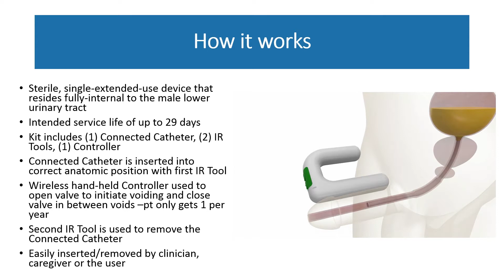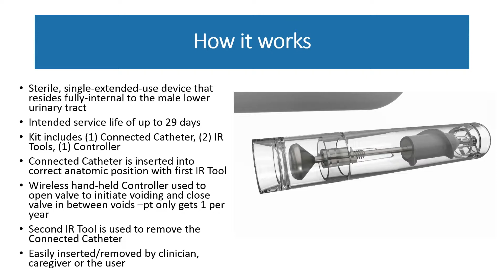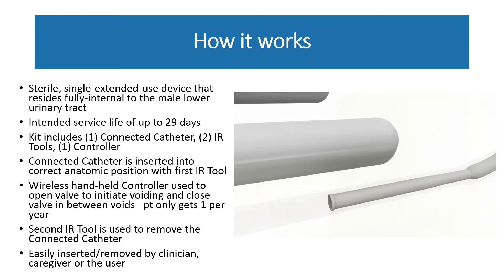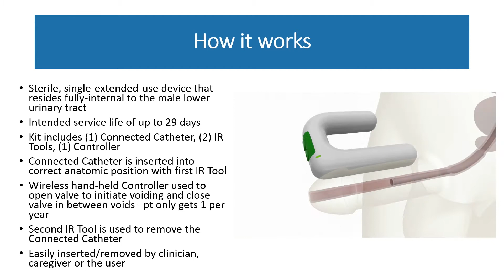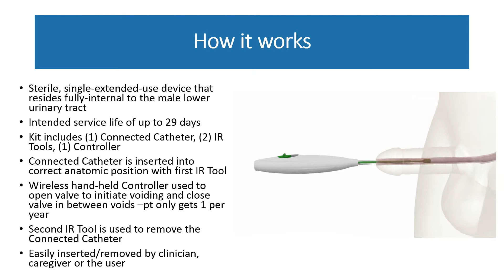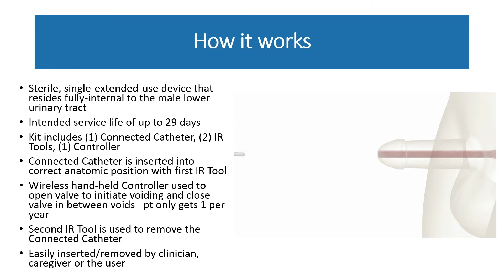Now this one doesn't have a turbine to drain it. This is actually going to be drained by gravity. Once it's drained by gravity, you'll then use the electromagnet again to sort of lock it in place. As with most all of these, they're just 29-day or 28-day devices, so they're not permanent implants. That's mainly due to regulatory processing of things. But it's something that would be in the office, easy to put in, and also easy to take out at that point in time. So when you take it out, you'll have the instrument tool that will go in and lock it in place. It's kind of a snare to be able to grab it and then slide it out.